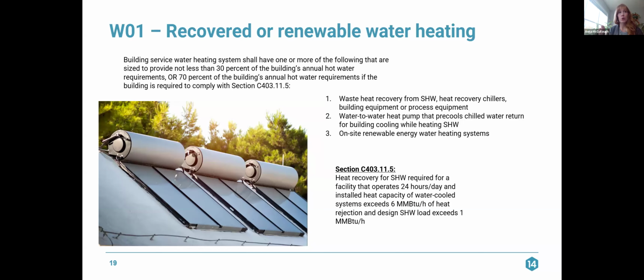requires, my goodness, heat recovery for service hot water for a facility that operates 24 hours per day and has installed heat capacity of water-cooled systems exceeding 6 million BTUs of heat rejection, and the service hot water load exceeds 1 million BTUs of heat rejection. So the only building type that I could think about that would achieve this would be like a giant hotel in the mountains that is providing water-cooled chillers, and they have like a huge spa, and maybe not even in the mountain. It would have to be in the, we'll say it's in the Front Range. But anyway, so just a giant hotel with like a spa and a huge pool, and they have this huge service hot water heating load.